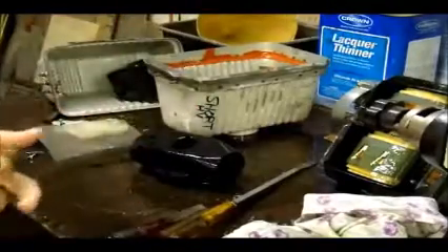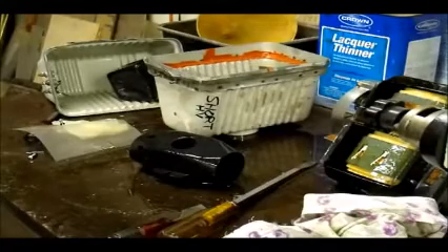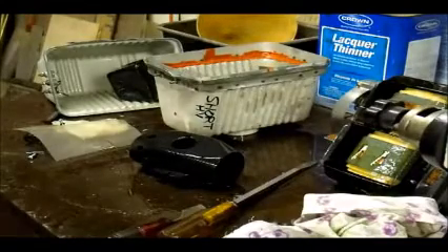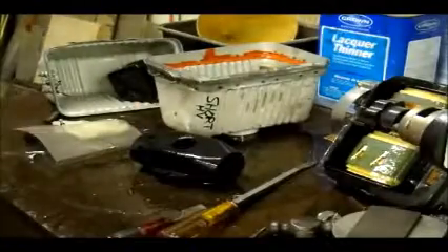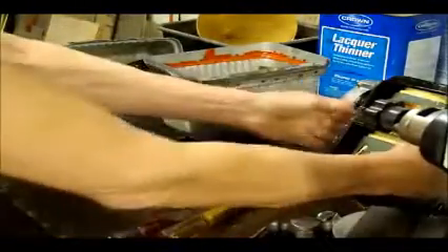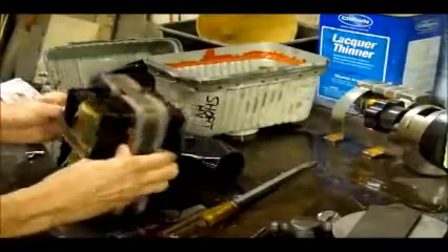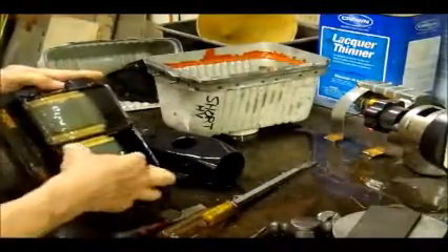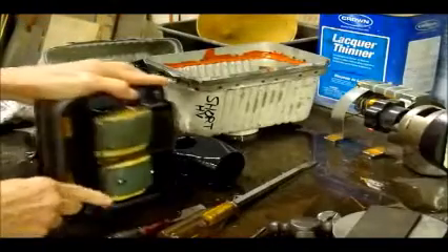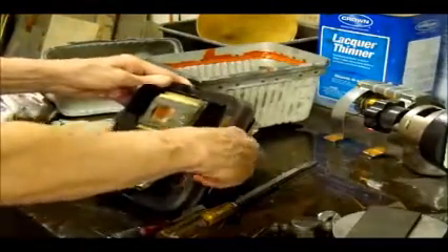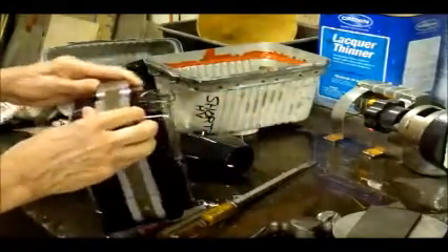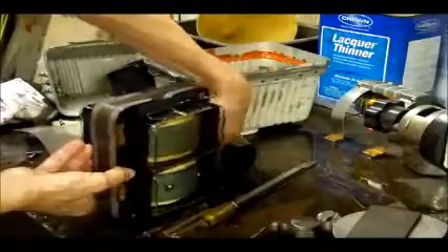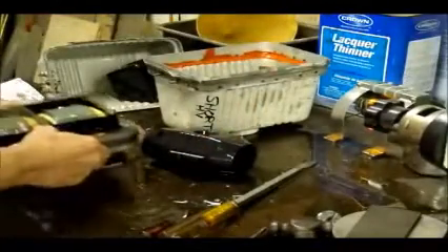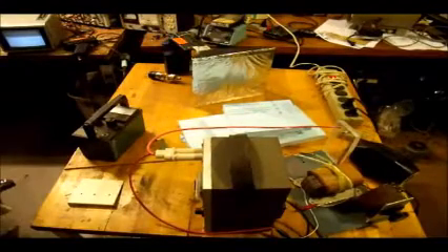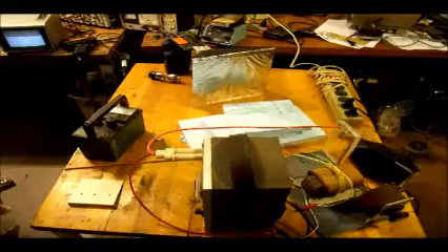Okay. So that's how we open up one of these Gendex X-ray heads. Now, see if we can see anywhere that we have a short here. I don't see any sign of arcing. The only way is to hook power onto it and see where the short circuit is. Because there doesn't seem to be anything wrong with it, which means we probably have a good transformer. Okay, we'll go ahead and test the X-ray tube now and see how it works.